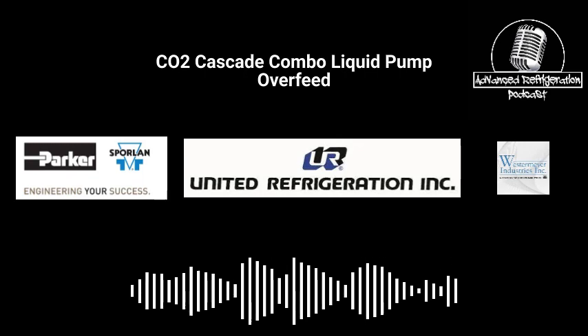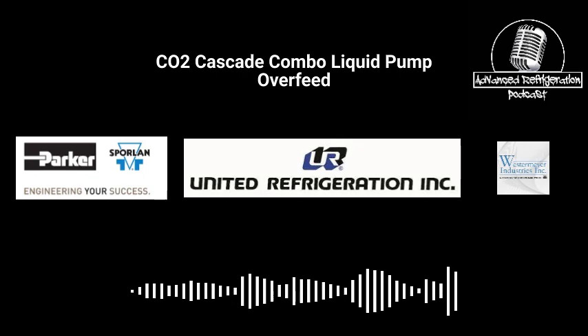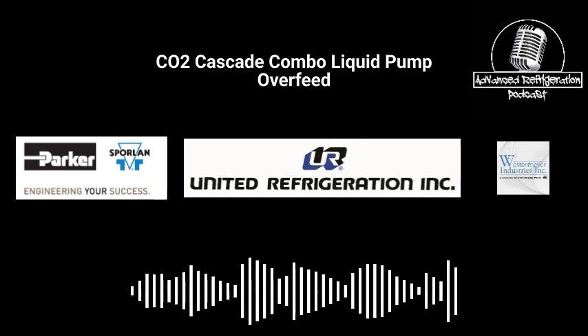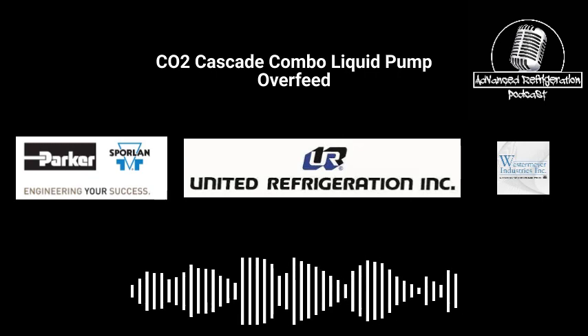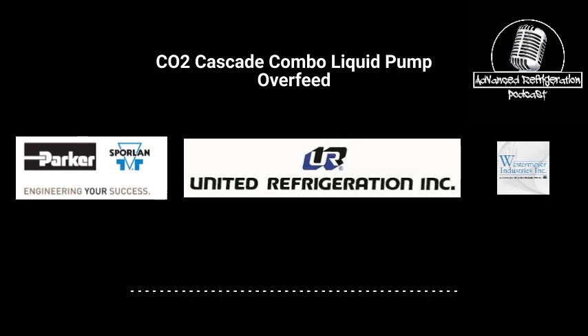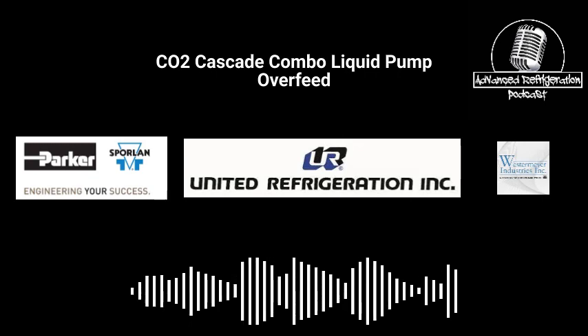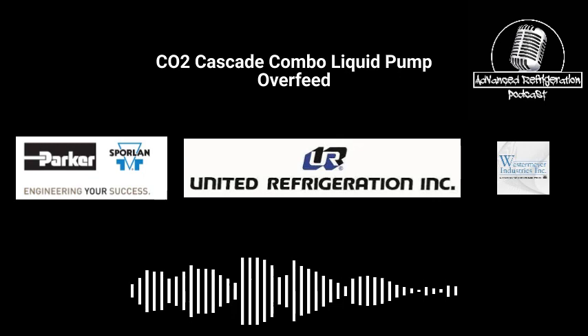Yeah, you're going to start seeing those Bitzer digitals a lot more because I'm pretty sure they just got approved for the CO2 compressors. So I'm pretty sure you're going to start seeing those a lot more, because obviously that's going to reduce the cost of VFD. But I don't know, on the CO2 side I'm not exactly thrilled to see that. I think VFD is a great idea, but we also have the harmonics issues. That digital may make the harmonics go away, but then you also make the actual superheat control worse, because your process variable, meaning your suction pressure, is changing all the time.